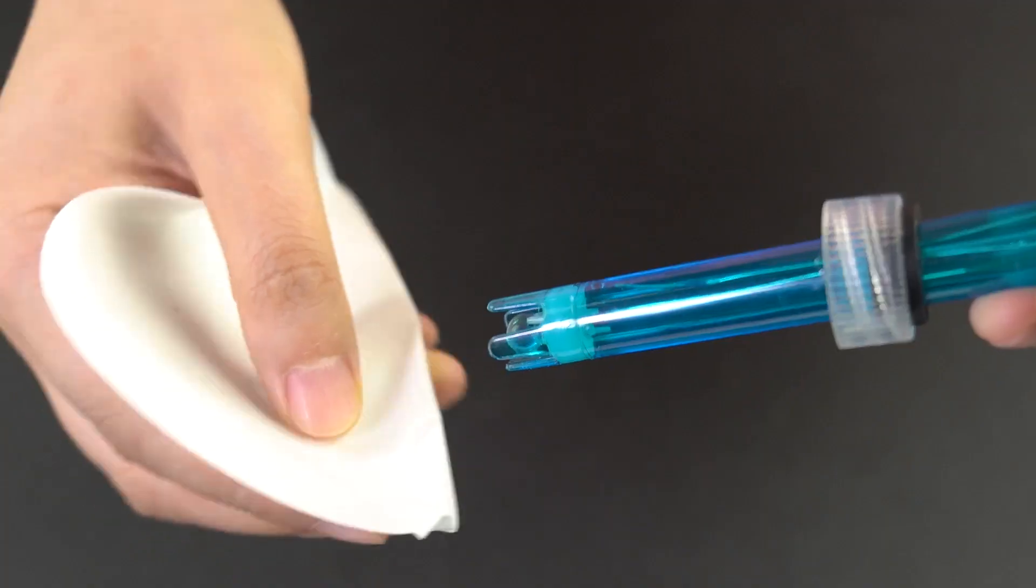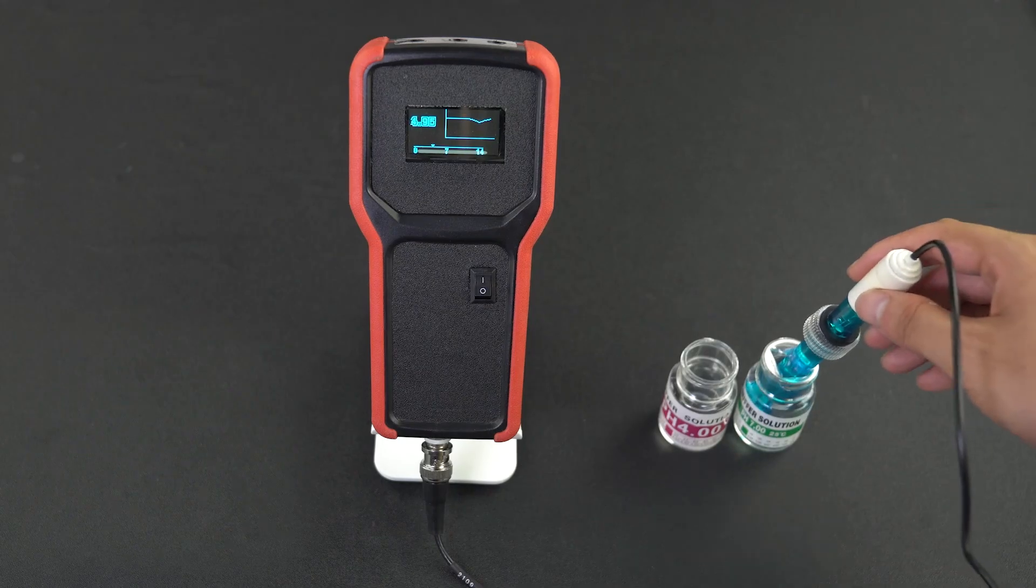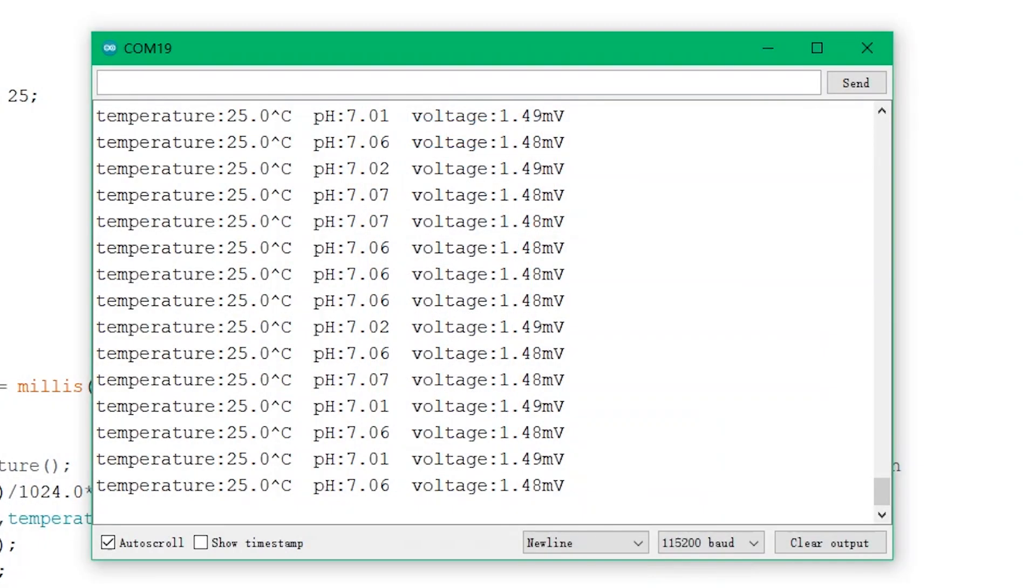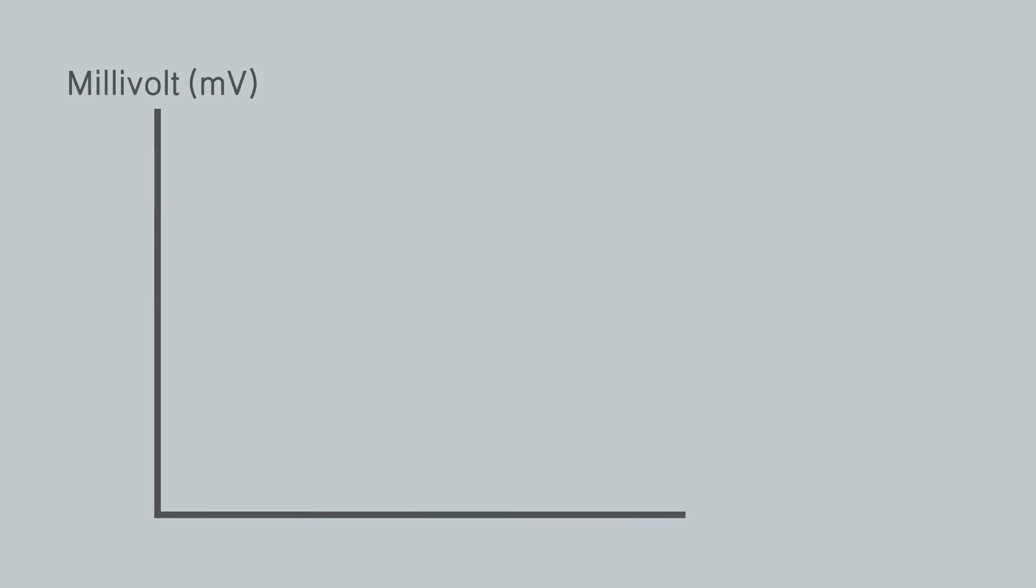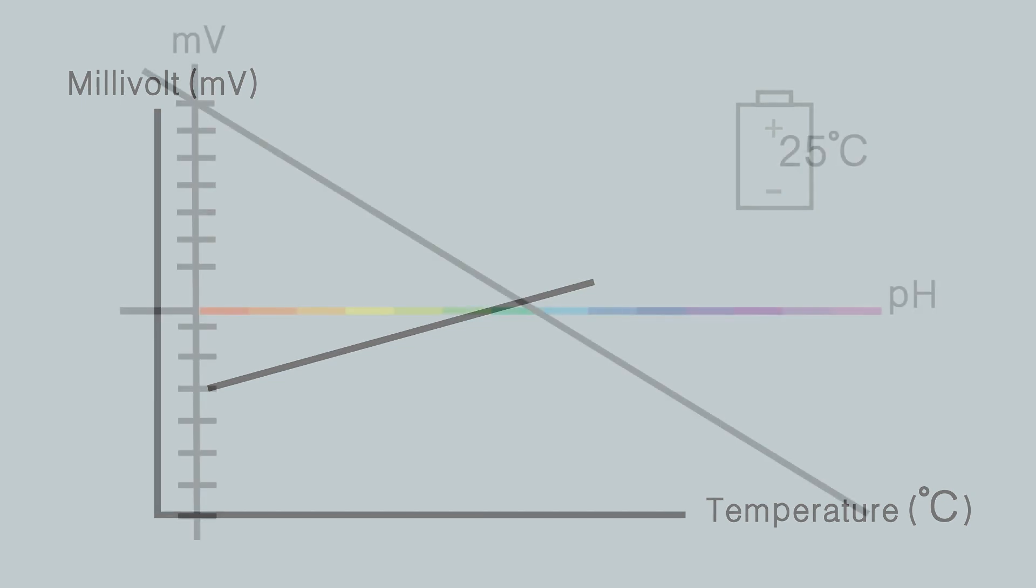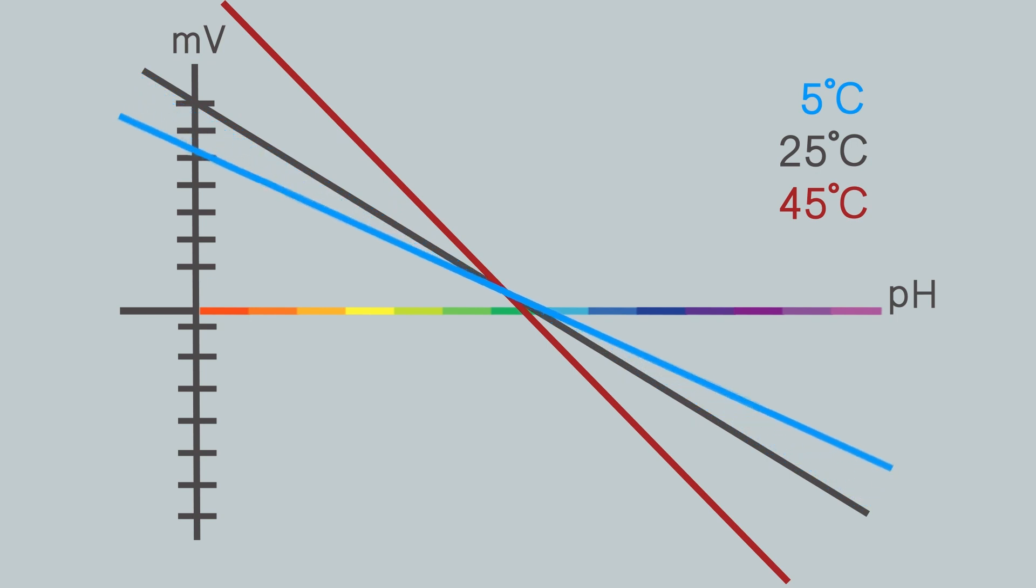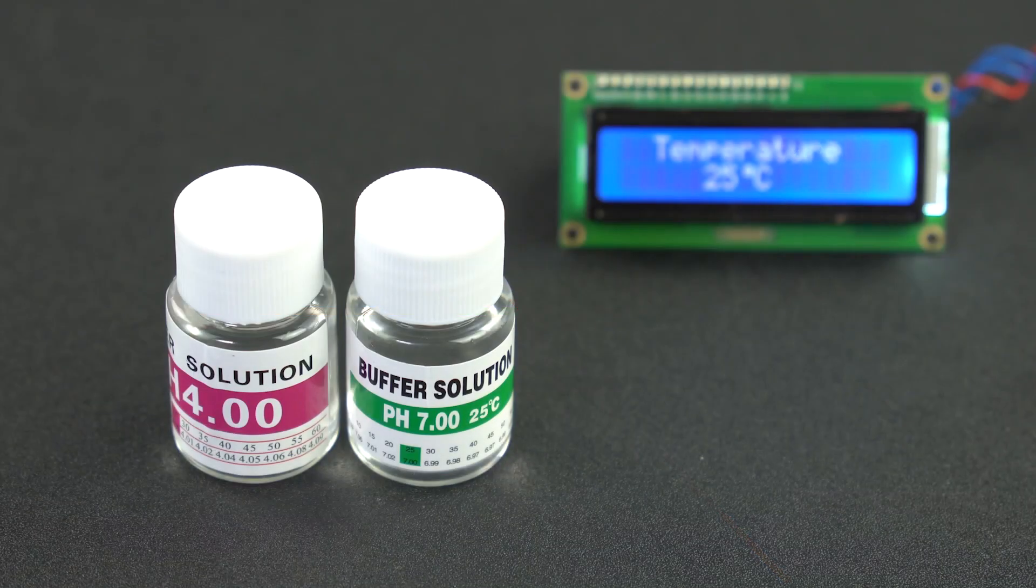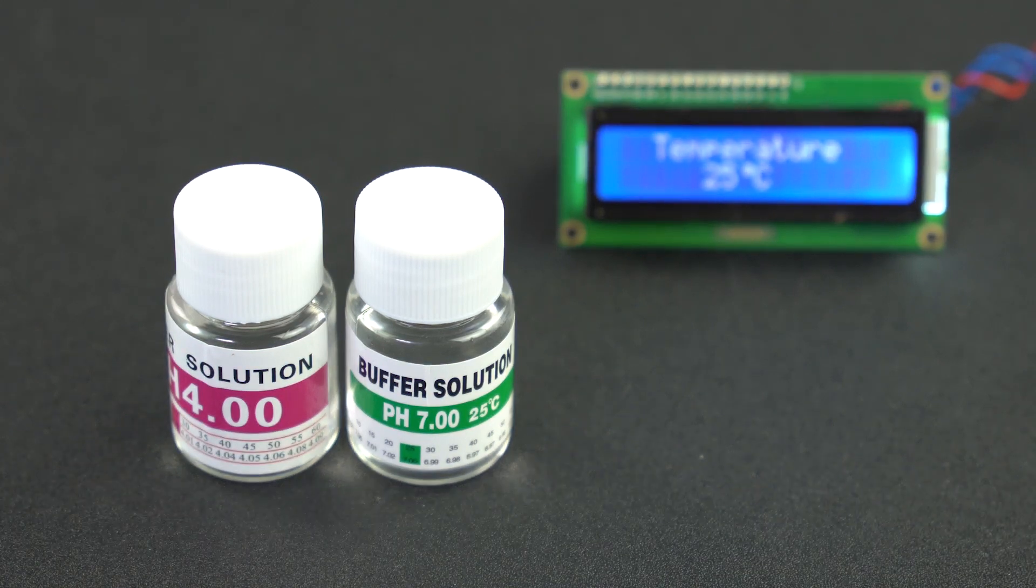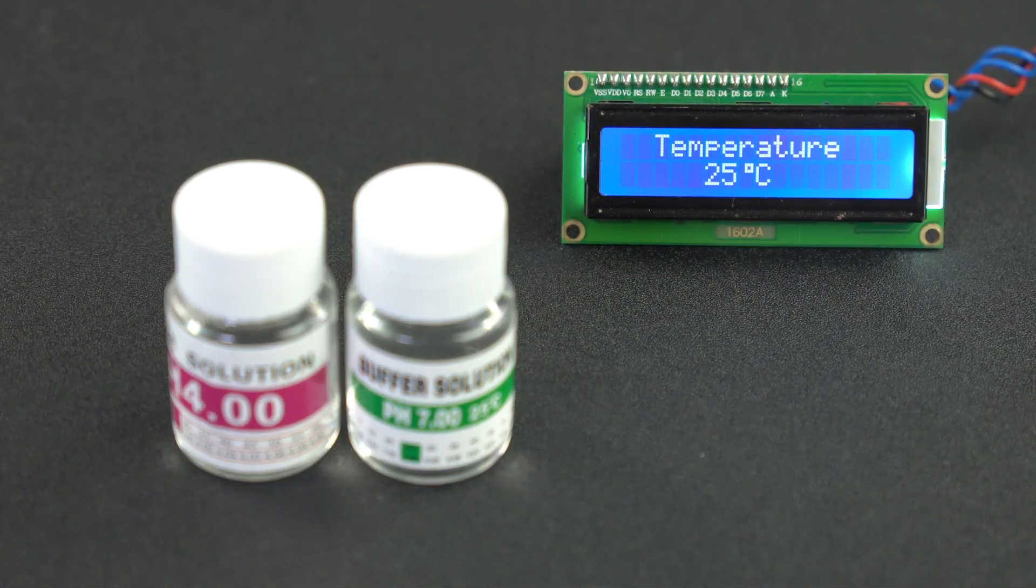Besides, temperature also affects pH measurements. The readings above are all obtained at 25 degrees Celsius. As we all know about batteries, the higher the temperature, the higher the voltage. Conversely, if the temperature is low, the voltage output is not as high as expected. Since temperature will affect the slope of the pH calibration curve, its impact on pH reading should be taken into account if the measurements are done at different ambient temperatures. It is best to use standard solutions with the same temperature as the solutions to be tested during calibration.